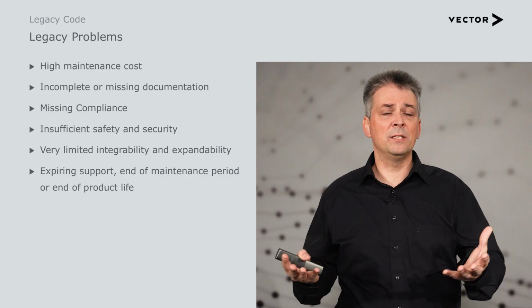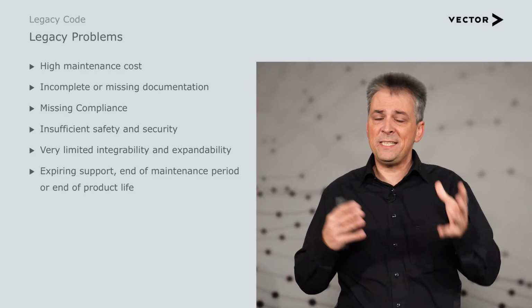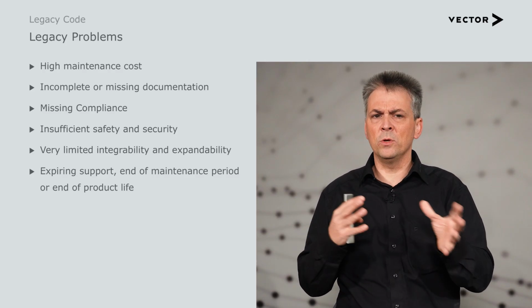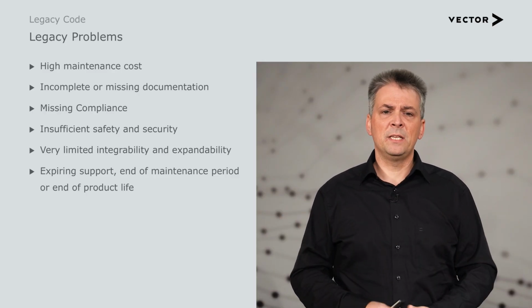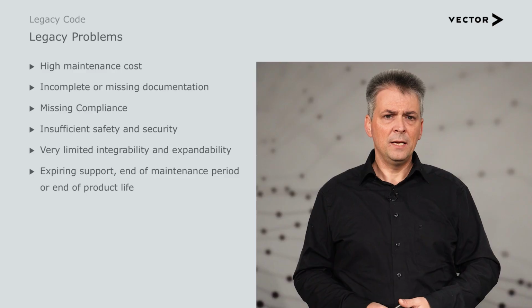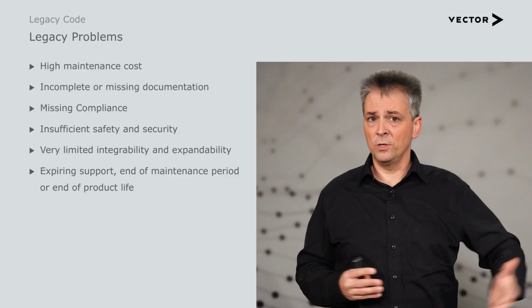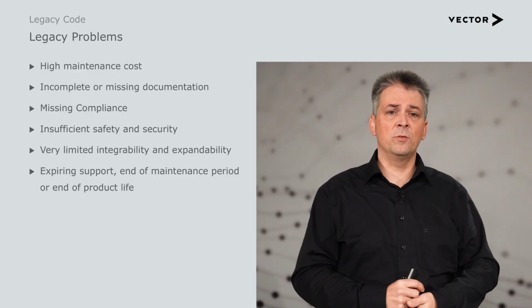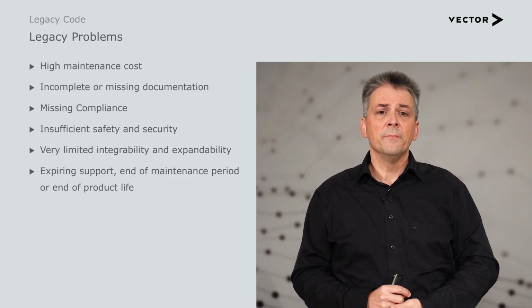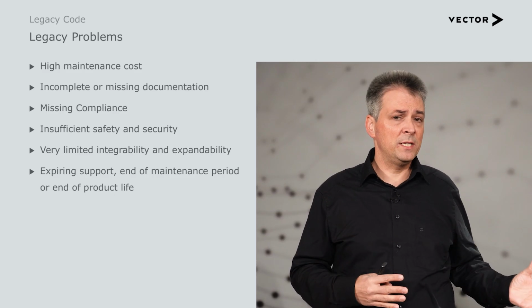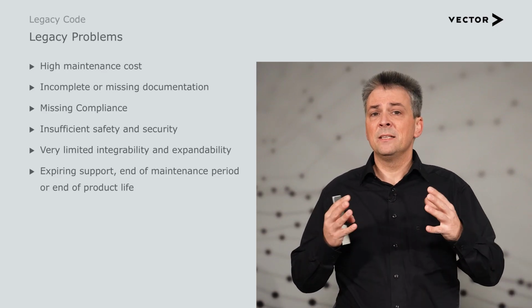So you have high maintenance cost. You always have to investigate, what does this code do if I want to change it? Then you have incomplete and missing documentation. It is not developed according to the current version of the standard, so there is documentation missing. Missing compliance comes with that. Insufficient safety and security, as already mentioned.